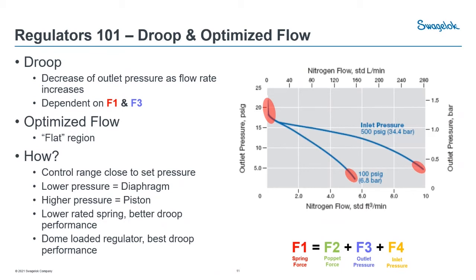Droop is mainly your decrease of outlet pressure as your flow rate increases. As flow demand increases, the poppet opens up more and more to supply gas through the seat. Going back to our balance of equations, this is dependent on F1 — our spring force — and F3 — our outlet pressure. As you turn down the handle, you increase spring force and that increases your outlet pressure. Reading this graph from left to right, as our flow demand increases, our outlet pressure starts to decrease — that's really what droop is. We want to be operating in this area, and if we can get this area to be as flat as possible, that's where we get the most predictability out of our regulators.